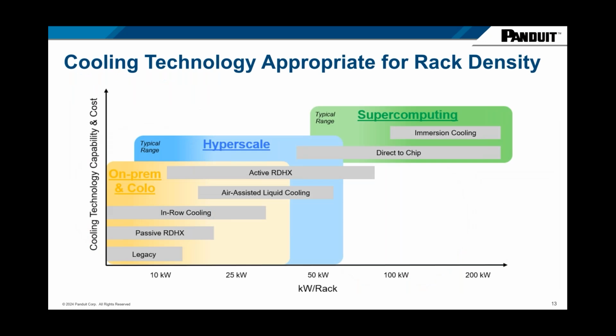This shows a bit about adoption - who's deploying what, where, when, and how. On the x-axis, air cooling is viable for the near, mid to long-term future. But when you get into 25, 30 kW, you move to air-assisted liquid cooling, active rear door heat exchangers. At 50 kW and up, you're looking at direct-to-chip. And when you get to supercomputing, the clusters, the hyperscalers, they're looking at immersion cooling going from 150 kW up to 300 kW. So this is an evolution of the technologies based on requirements, and the expected adoption rates by segment.